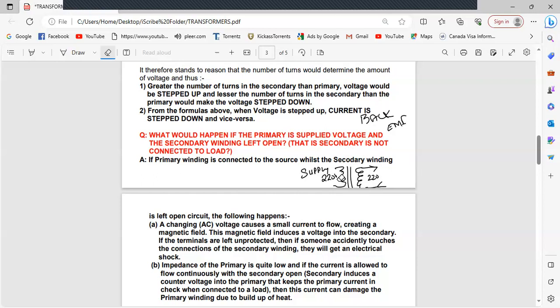It's going to increase tremendously, and when the primary current increases tremendously, the heat dissipated also increases. It keeps heating and heating. Remember, any device that goes 10 degrees beyond its normal operating temperature has its insulation fall by 50%. So the current flowing in your primary is so high that within maybe 30 or 40 minutes, your primary is going to be burnt out.